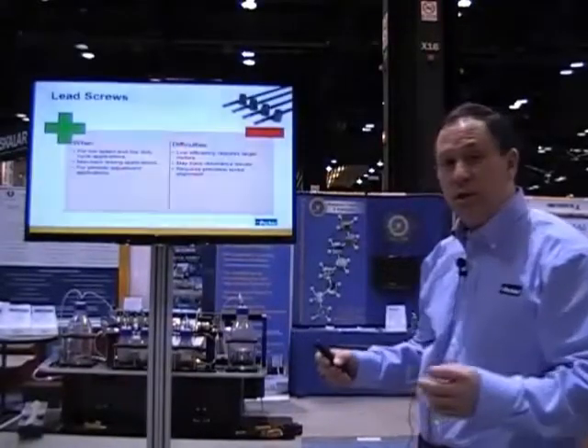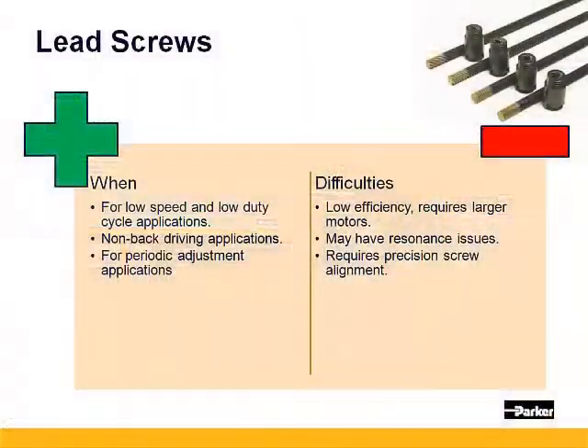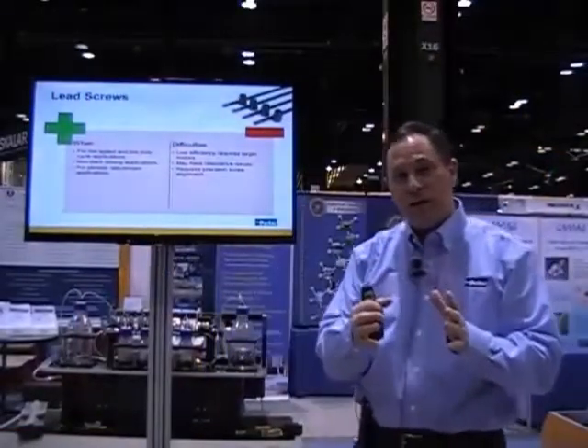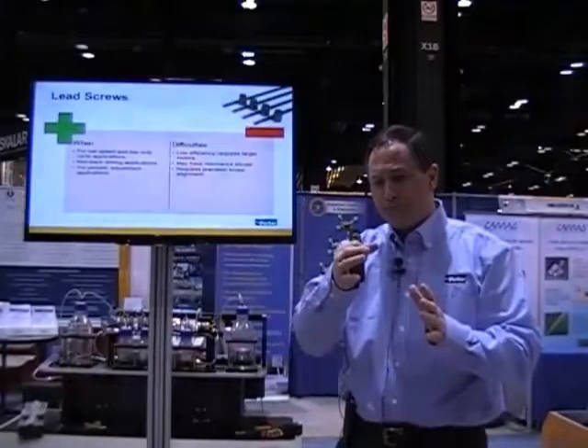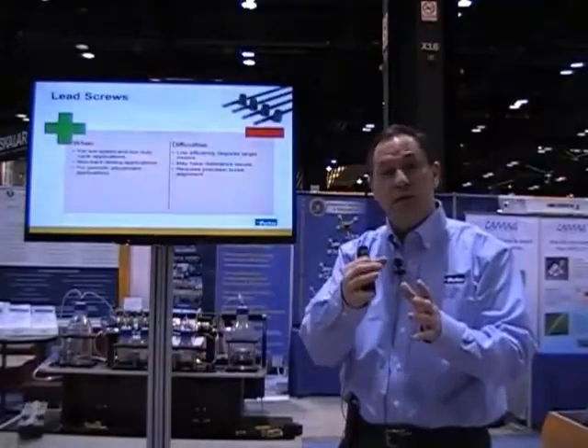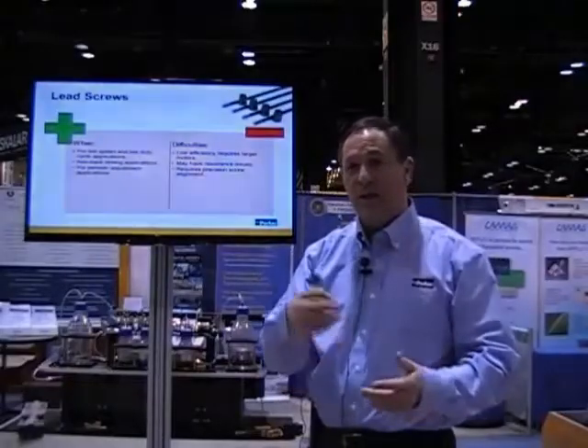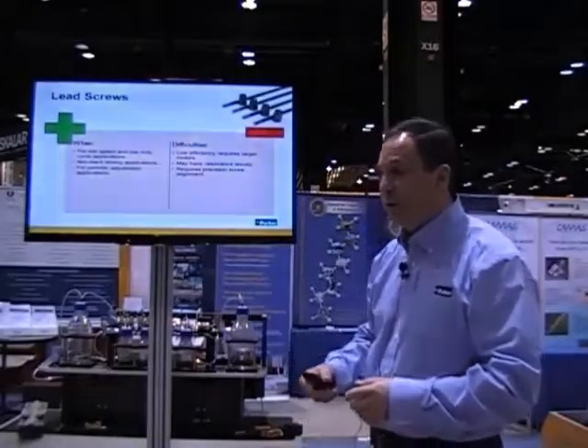Lead screws — this is a perfect technology if you have something that you're doing for low duty cycle, adjustment-type applications. They're inexpensive and easy to use. They also have non-backdriving abilities, meaning if you get the right lead screw and you're on a vertical axis, the load will not back-drive down. The screw is self-locking — it's about the only device out there. All other devices tend to need counterbalancing or something like that to prevent them from falling.